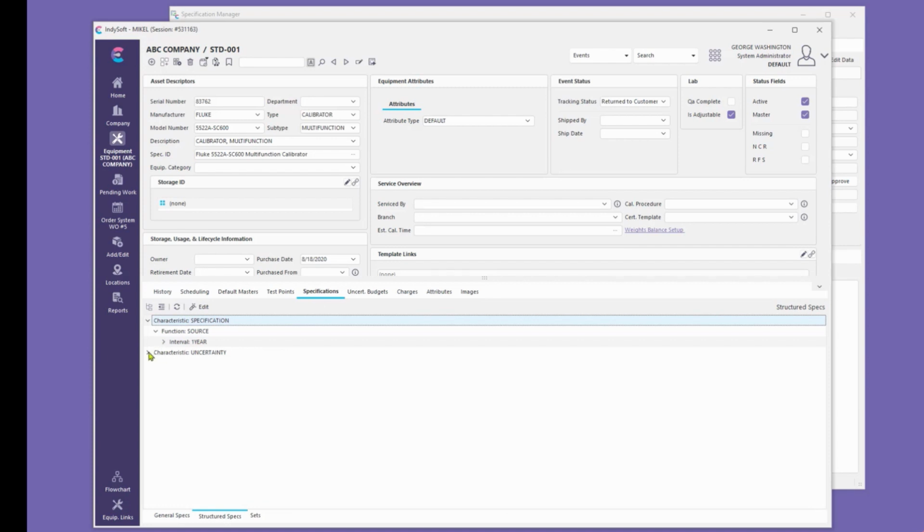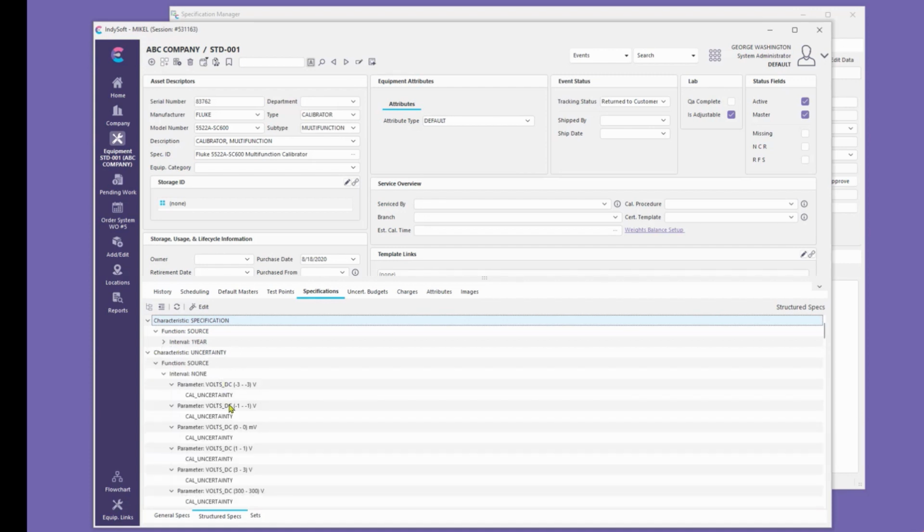This is also where we would store our inherited calibration uncertainty for this particular device. So when you get the certificate in from the manufacturer or whoever it is that's calibrating it for you, that data would go here, and now we have a place to look it up for our uncertainty budgets when this device is being used. So we also have a new concept.